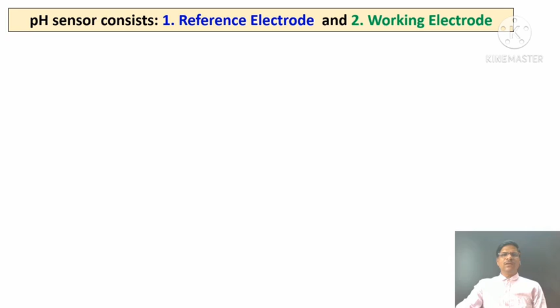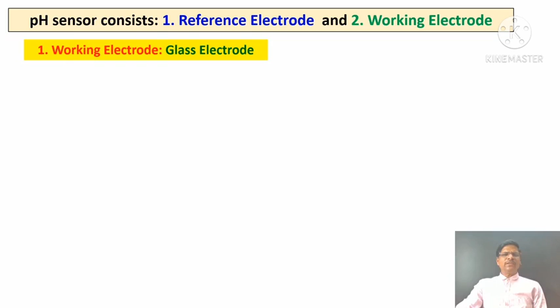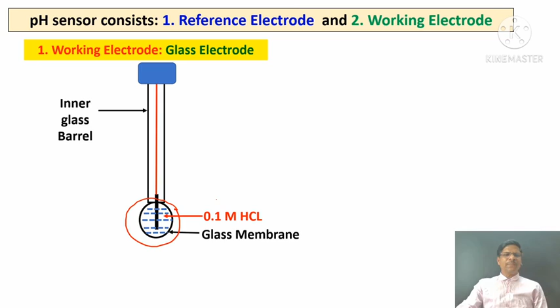If you see the pH sensor, it consists of two electrodes, the reference electrode and the working electrode. The working electrode is the glass electrode. It consists of a glass tube, and at the end of the glass tube, a glass membrane is attached. This is called the glass membrane, which is sensitive to the H+ ion. Inside the glass bulb, 0.1 molar HCl is filled, along with a silver chloride wire. This is the construction of the glass electrode.